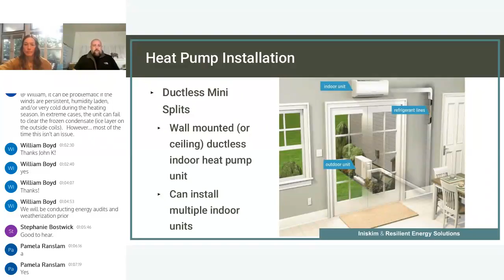Next slide, please, Steph. And so that brings us to the mounting of the indoor unit. So this case has the head unit, and it's running all of the refrigerant, power, and condensate lines up to the attic. We would try to avoid this, as the condensate line, again, should be able to flow naturally by gravity and not have to be pumped up to get out of the house.